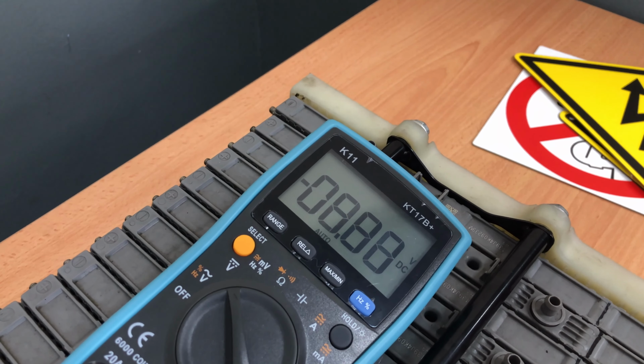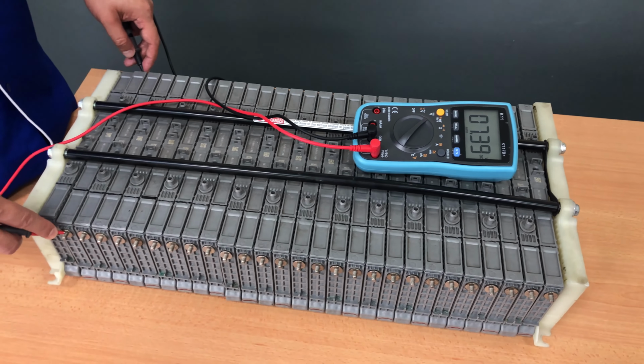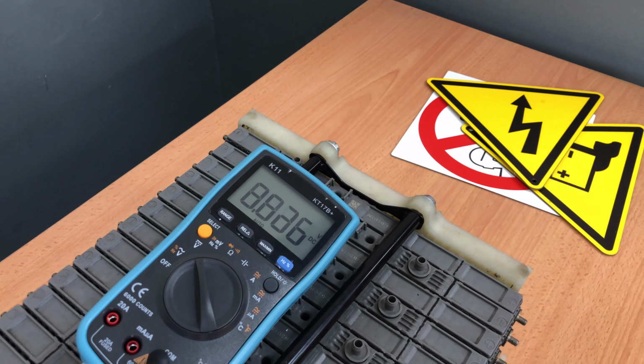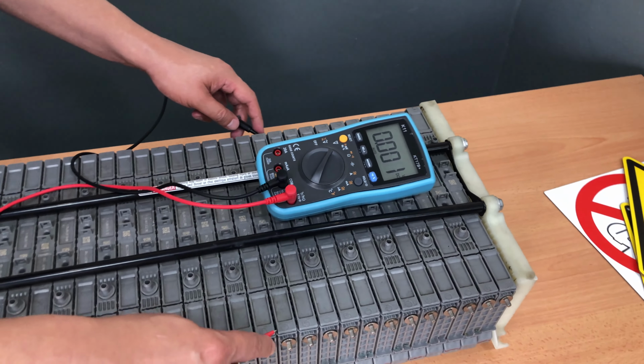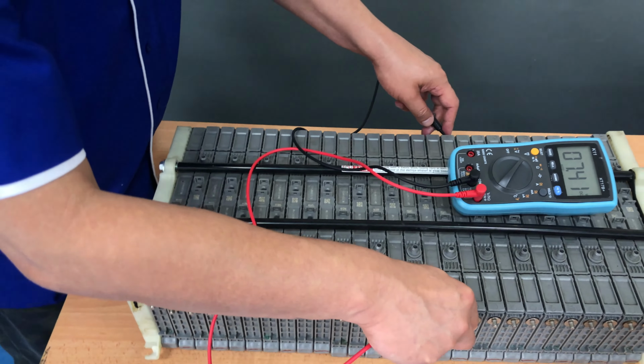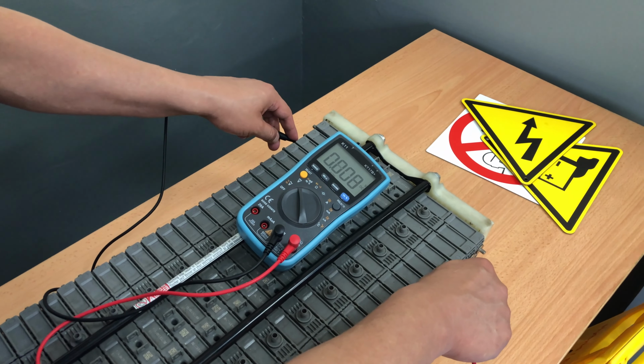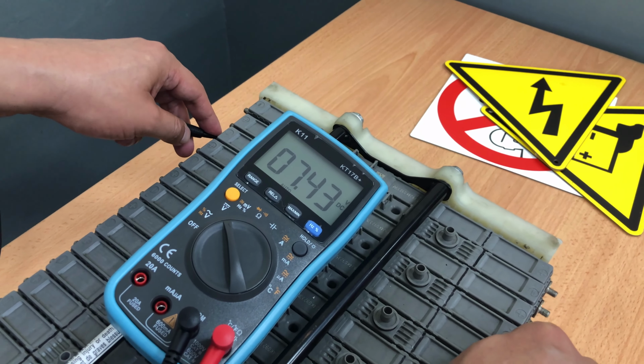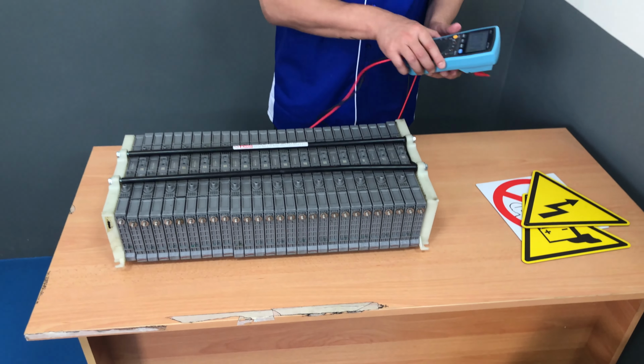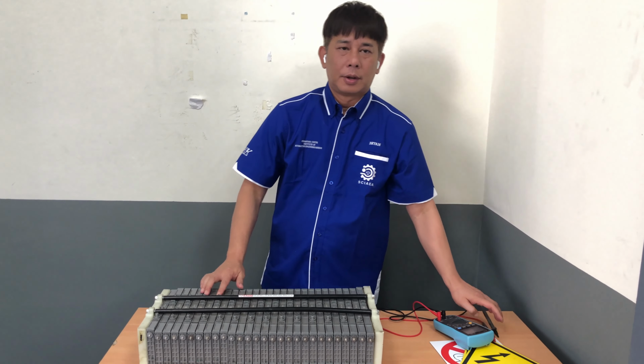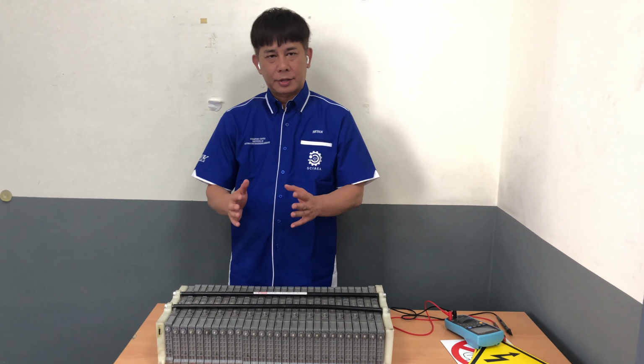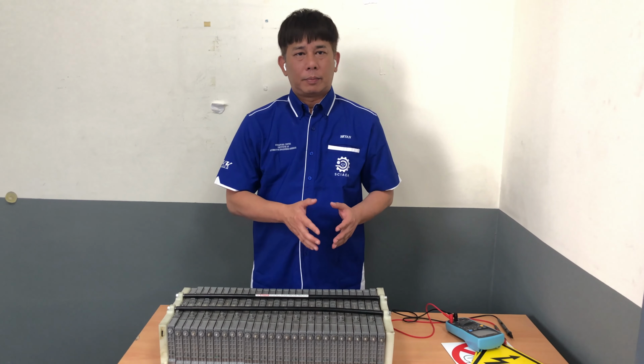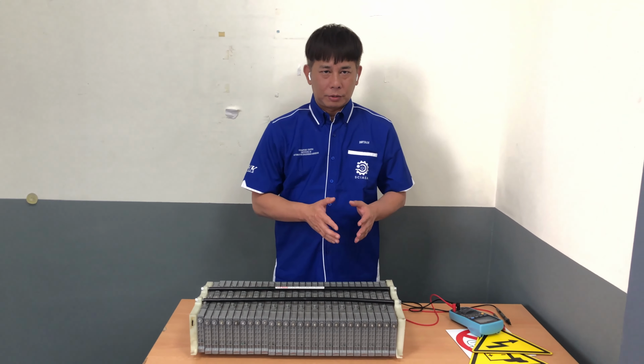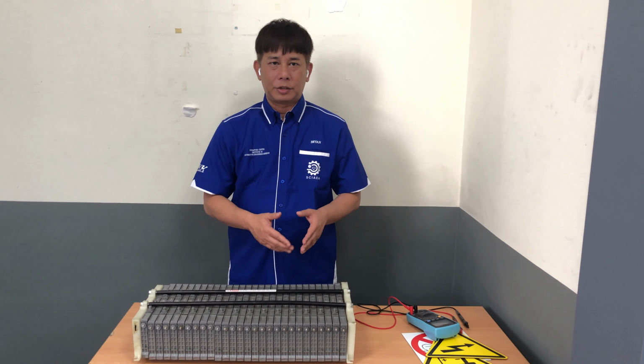So what we have is 7.40 volt DC, and the next cell will be 7.39 volt DC. And then if we move on to other cells, we have 7.4, and then we go into 7.41, and towards the end we have 7.43. Now the purpose of this is basically to check if there is any imbalance in the individual cell. Because if you have a cell that is below the manufacturer's standard voltage, you would know that that cell is a bad cell and it needs to be replaced.